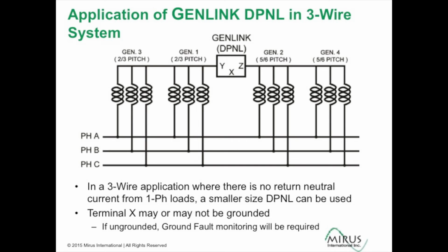If you want to ground it, but you don't need to connect the neutral, because you don't have phase to neutral load and so you don't need a neutral return path, then you can ground the DPNL at the X terminal. And in these applications where there is no return neutral current, the DPNL can be sized smaller than it would be when it has to handle the return neutral current in a 4-wire application.